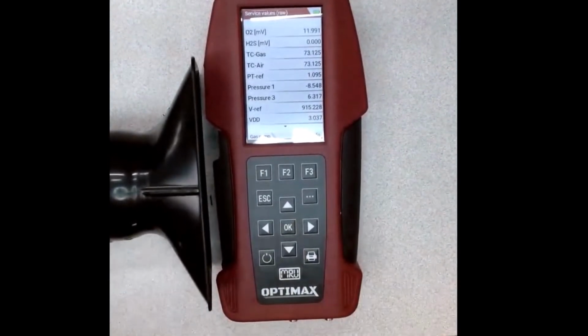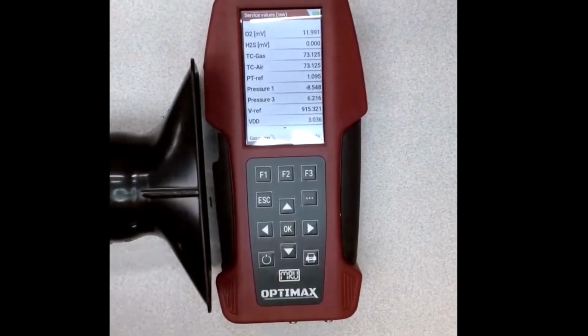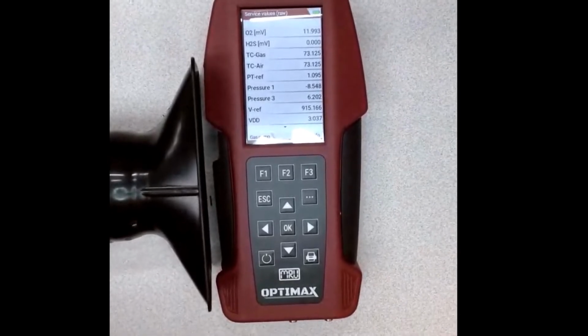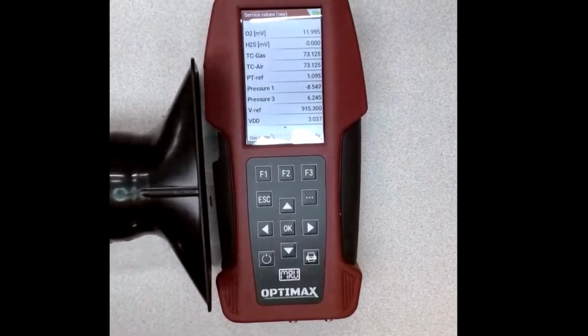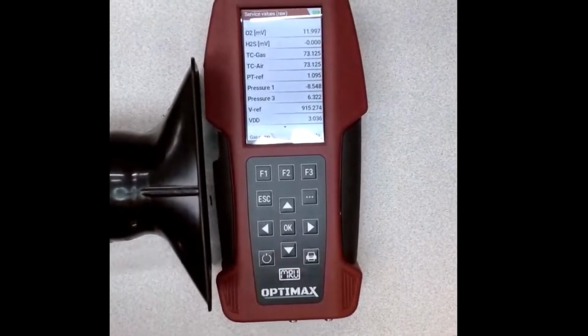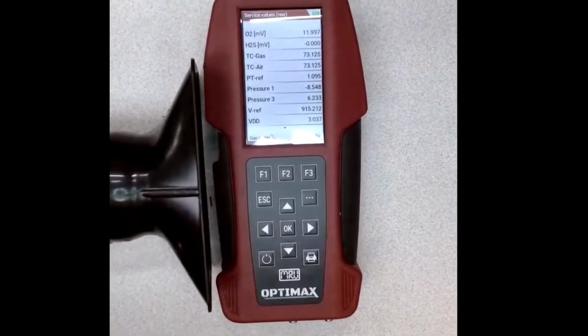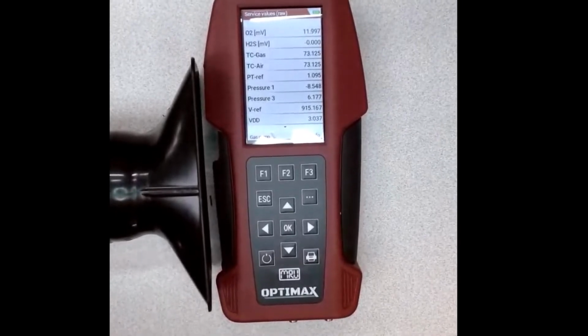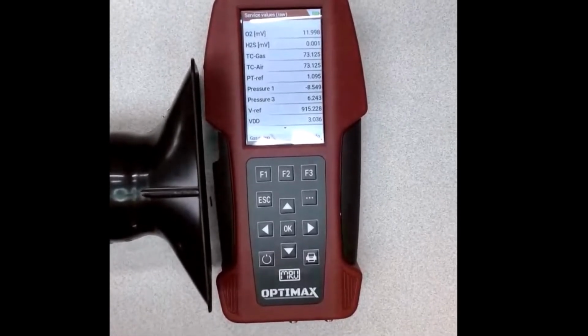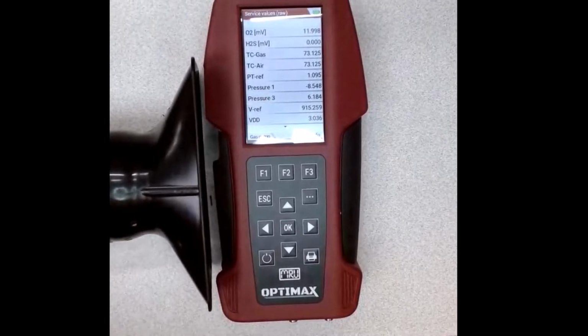Once we enter the service values menu, the pump will begin running, and this will allow fresh air to go over the sensors and for the whole system to be purged, and will allow the sensors to stabilize. For field calibrations, we recommend a sample time of 10 to 15 minutes after turning the analyzer on for optimal fresh air purge.